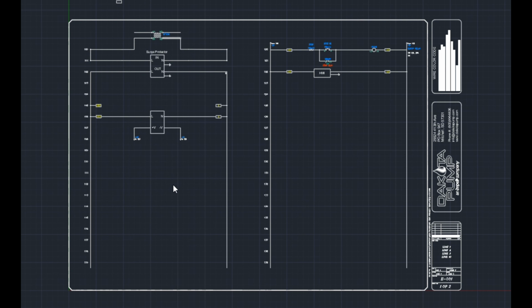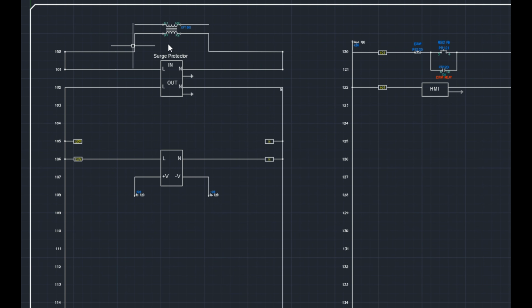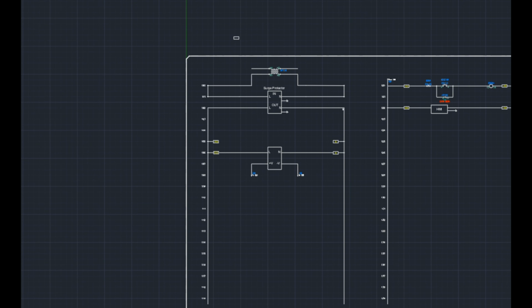So this here is the pre-built, or as much pre-built as I could find, of my schematic drawings. I couldn't actually find my pre-build drawings, but this is before my analog cards went haywire, so I did have to do a bunch of editing to get my project to work, but this page didn't change at all. This is pretty straightforward wiring and whatnot. I have my transformer with 2 phases of my 3-phase 240 coming in, and then coming out is my 120, and my neutral going to my surge protector, which is feeding my DC power supply, which is feeding the rest of my drawings.